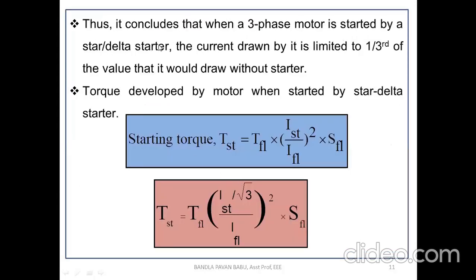Thus it is concluded that when a three-phase motor is started by a star delta starter, the current drawn by it is limited to 1/3 of the value that it would draw without a starter. We have seen the DOL starter; for some other starters we require additional devices, but with the help of a simple changeover switch we can limit the starting current. The extent to which we can limit it is 1/3 of the short circuit current.